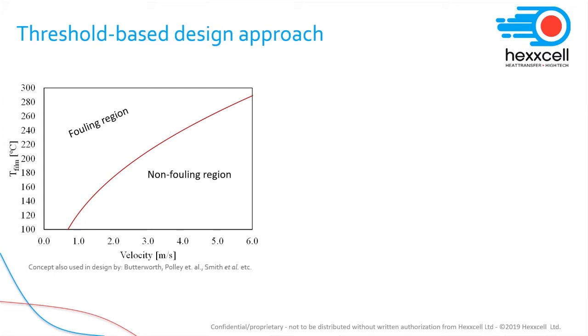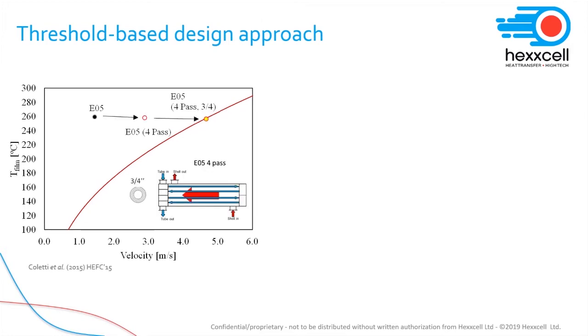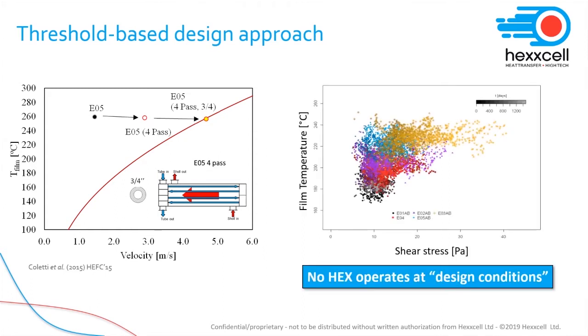The existence of this threshold can be used to determine the conditions at which a heat exchanger does not foul. Above the threshold, the heat exchanger is in the fouling region. Below it, it does not foul. The trick here is that knowing where the threshold is allows us to move the design point of a heat exchanger from above the threshold to below the threshold. However, there is no such a thing as a heat exchanger operating at the design point. What I'm showing here on the x-axis is the shear stress, and on the y-axis the film temperature for 5 heat exchangers over a period of time. Each dot represents a day of operation, getting brighter with time. Colors indicate different heat exchangers. As you can see, each heat exchanger changes operating point over time. This is both because of the changes in inlet conditions from operations and because they are affected from fouling. So if we want to apply this concept to eliminate fouling, we should make sure that the heat exchanger is operating below the threshold at all times during operations.